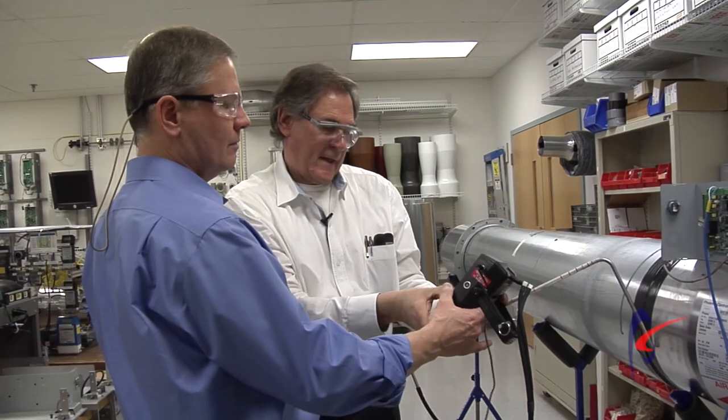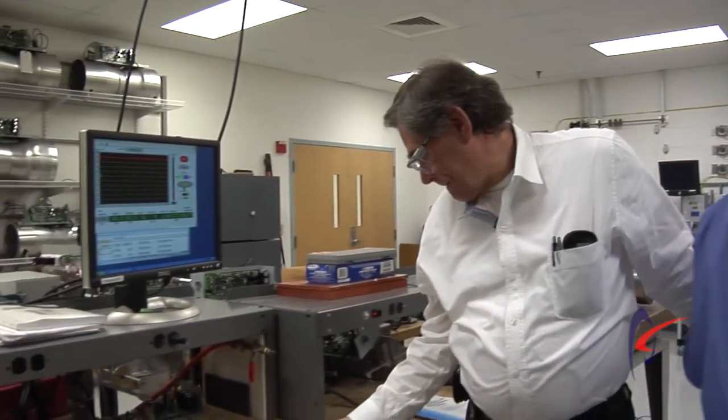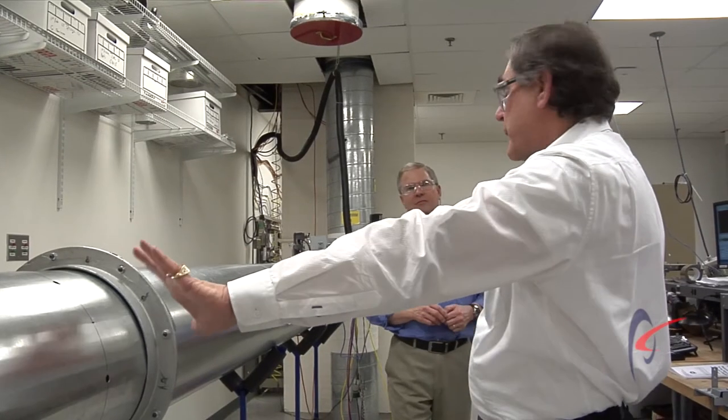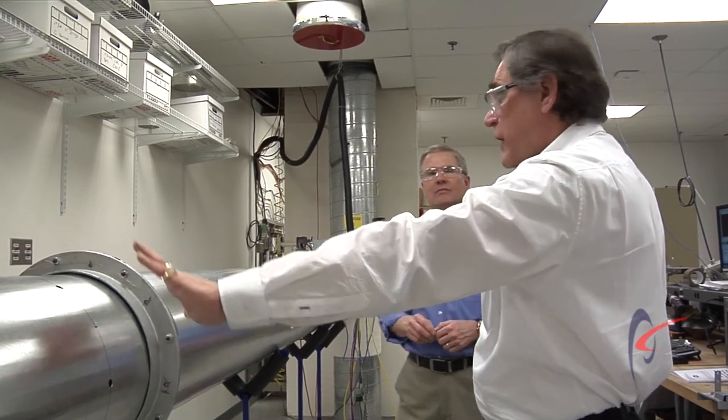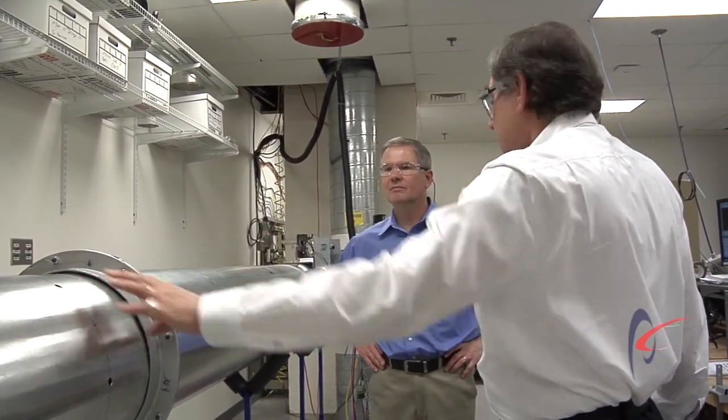One of the experiments we ran at Phoenix was to compare the results that we got from a pitot tube traverse that was conducted downstream of a valve in a relatively long section of ductwork so that I had no turbulence and nice uniform flow.